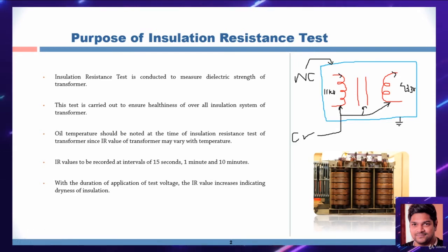If a high voltage winding gets connected to the transformer body somehow from the inside, it will result into a ground fault. The entire high voltage will get connected to transformer body, which is placed on the ground, which will cause a severe ground fault. Similar thing will happen in case of low voltage winding. Also, if a low voltage winding and a high voltage winding get connected electrically, what will happen? Again, a very unsafe scenario. It will be a phase-to-phase fault.